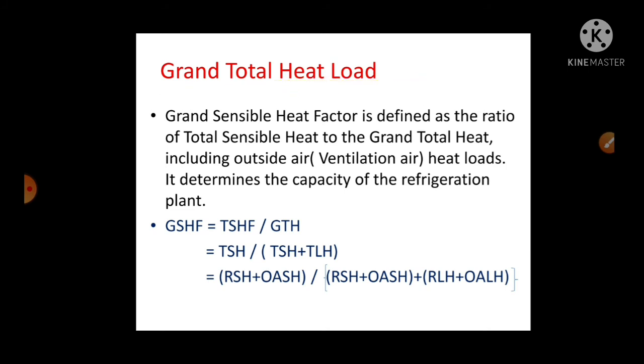OK. So including outside air heat loads, it determines the capacity of the refrigeration plant. What is your grand total heat load? Grand sensible heat factor, याला म्हणतात grand sensible heat factor, is the ratio of grand sensible heat divided by grand total heat. So what is grand total sensible heat divided by total sensible heat plus total latent heat?